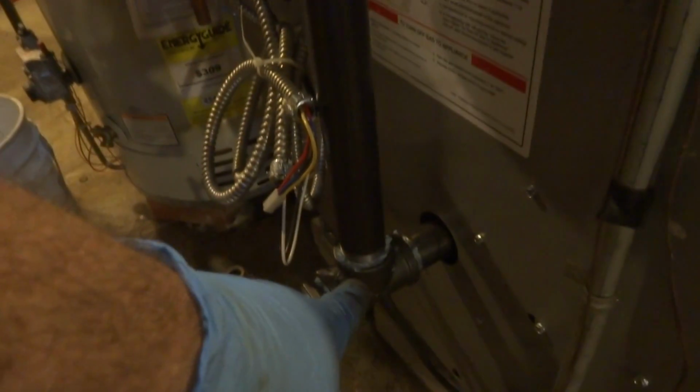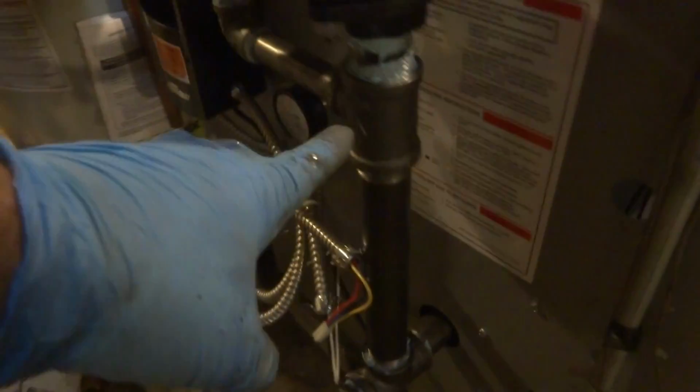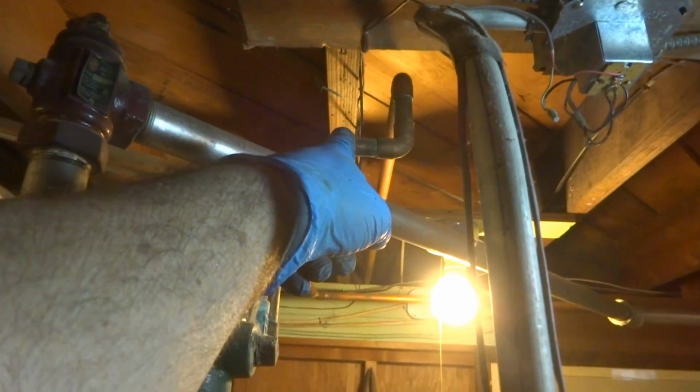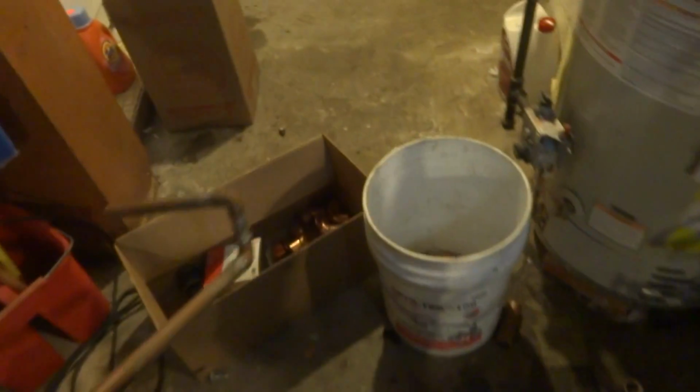I did come up with this factory piping, and I put this 12-inch nipple in. 1.25 by 3/4 T. 3/4 picking up, 1.25 picking up the first floor. There's going to be 2 elbows right on the return, and the supply will go up and tie into the return. I got to put a purge station in here. I'll put that on a piece going over there so I can purge the air out in the basement zone.